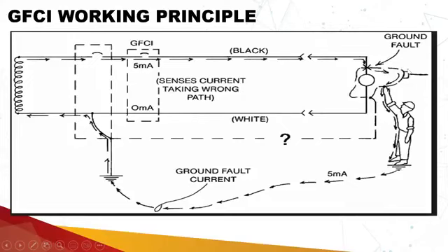So if this socket is being used for 10 ampere and I'm plugging in 20 ampere on that, the GFCI will not trip, because the GFCI will see that 20 ampere is going and 20 ampere is returning back into the circuit. That means there is no leakage there. Who should trip? The overcurrent protection device should trip, which is basically the watchdog for overcurrent, whether there is overloading or not.